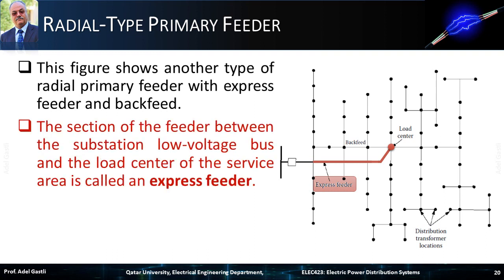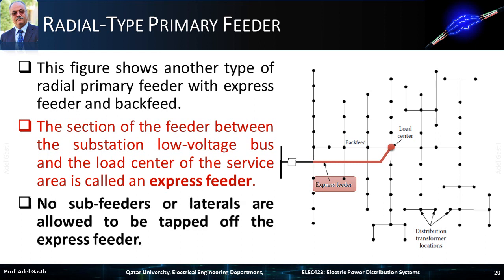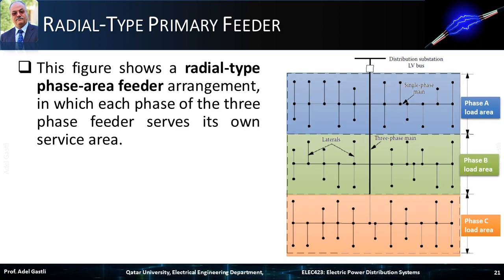The section of the feeder between the substation low voltage bus and the load center of the service area is called an express feeder. No sub feeders or laterals are allowed to be tapped off the express feeder. This figure shows a radial type phase area feeder arrangement, in which each phase of the three-phase feeder serves its own service area. Phase A serves the upper load area shown in blue, Phase B serves the medium load area shown in green, and Phase C serves the bottom load area shown in orange.